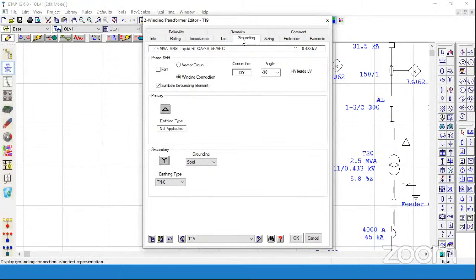Then the grounding section: how the transformer is grounded, and what the winding configuration of the transformer is, whether it is a delta star or star star transformer. So here we have a delta star transformer. Delta is on the primary side, star on the secondary side, and the star is grounded with a solidly grounded system.